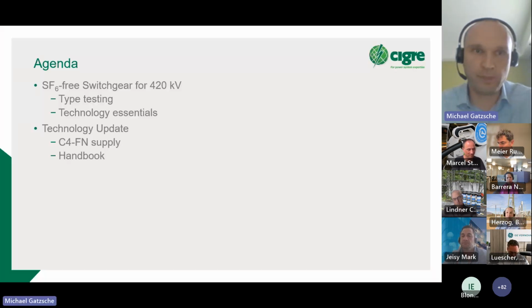For Birmingham, I would say from our side there were two focus points that I would like to highlight today. The first one is the SF6 free switchgear for 420 kV. Here we had a detailed update on the type test. I will show some excerpts from this, and also address the technology essentials necessary to have 420 kV SF6 free switchgear. Then I will give a general technology update. Here there were two topics that were often discussed: the C4FN supply and the handbook, for which Robert already gave some indication.